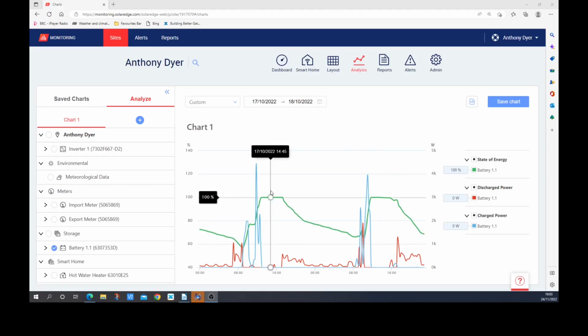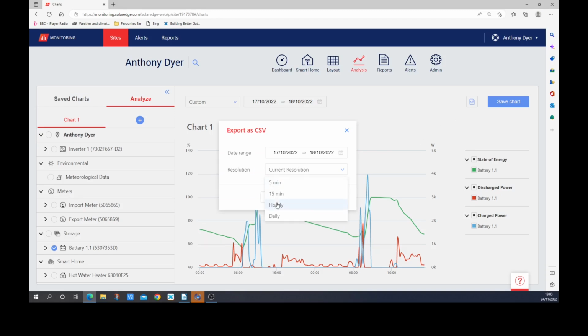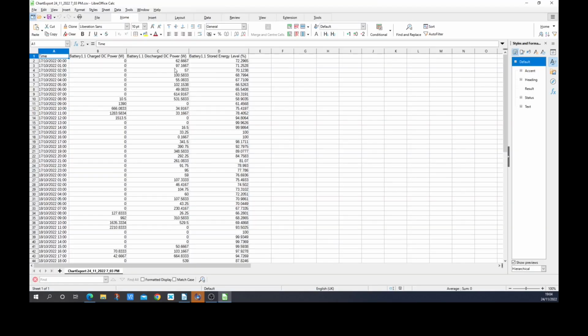What I did previously was I logged power consumption over a period from one full state of charge over to the next. And in this instance, I aggregated the discharge power and the charge power together. And the amount of discharge power integrated over time would be your discharged energy, and vice versa for your charge power integrated over time. If we output this in an hourly format, you can see that we have got units of power for each hour of the day.